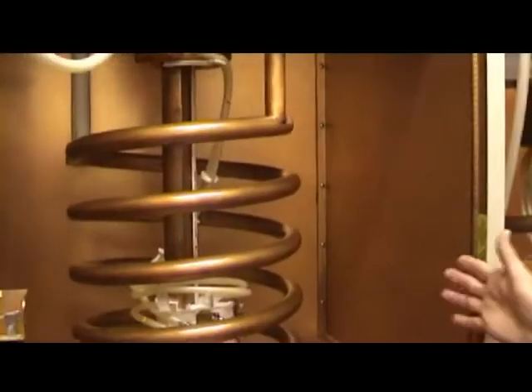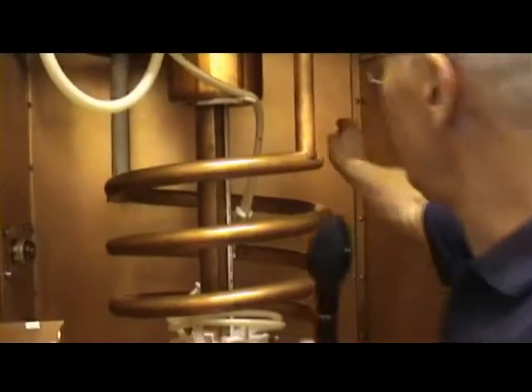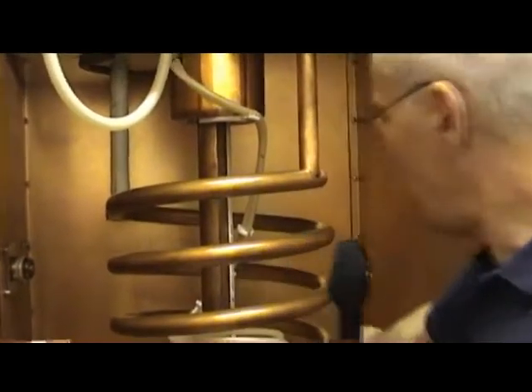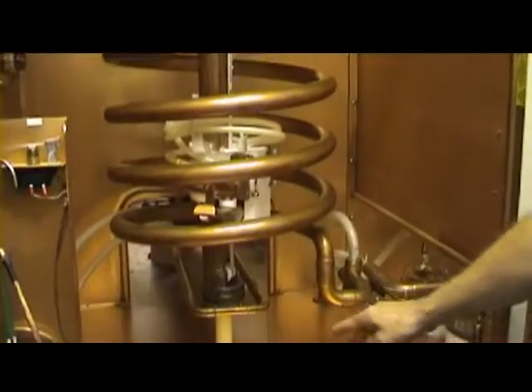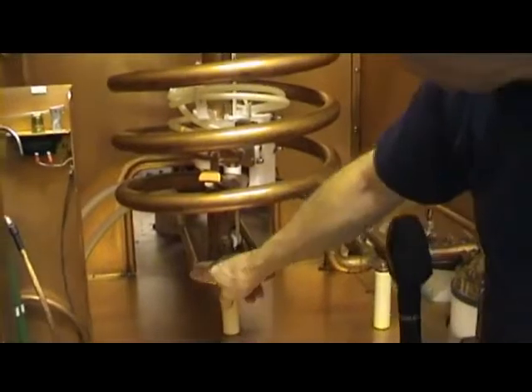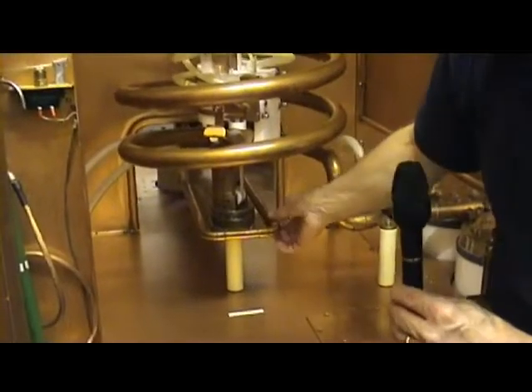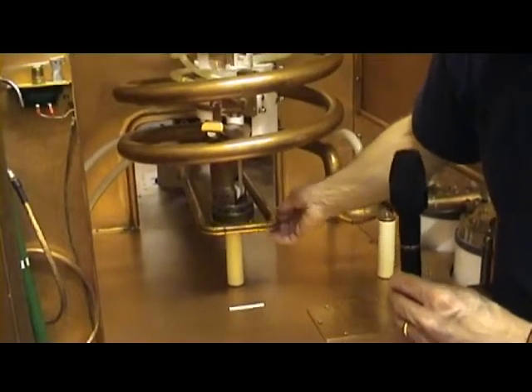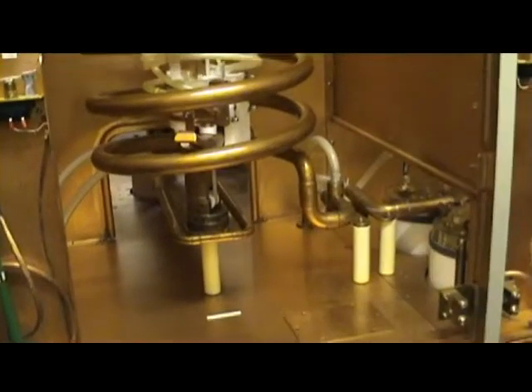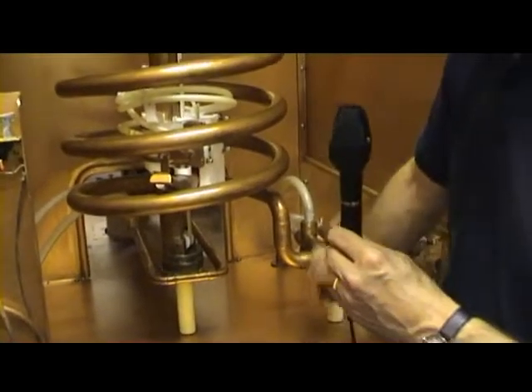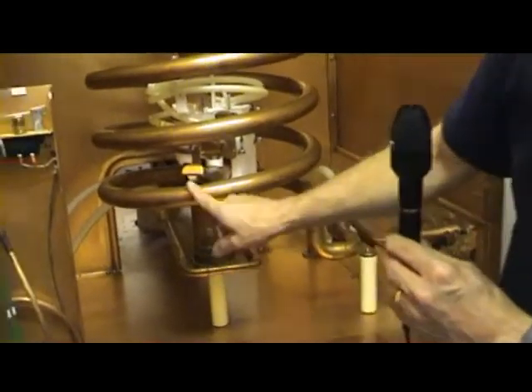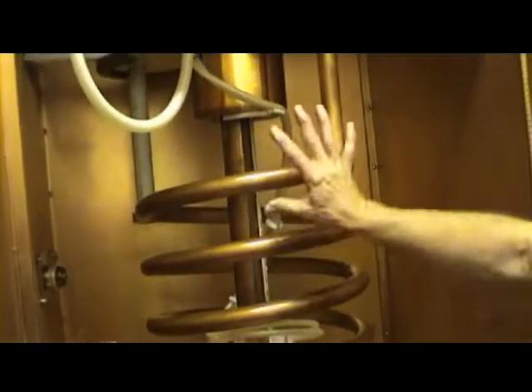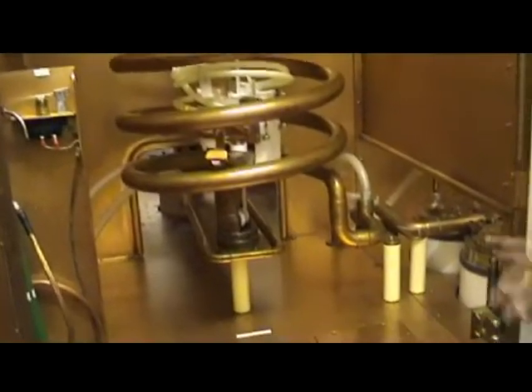We're in the front of the sender now. And the valve is behind this section here. And the RF output then comes through. Notice the edges, water cooled, so that the RF doesn't burn the edges of the copper. All water cooled. It hits this first inductor. There's one end of it, shorts round to there. This section's short circuited, not in use at the moment. So only using that much inductance on that section.